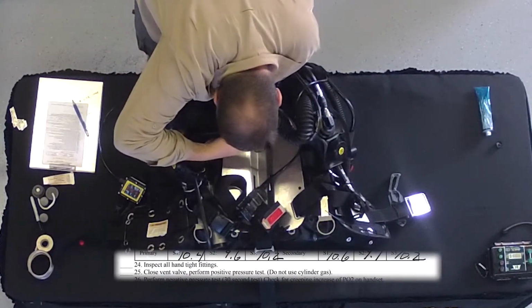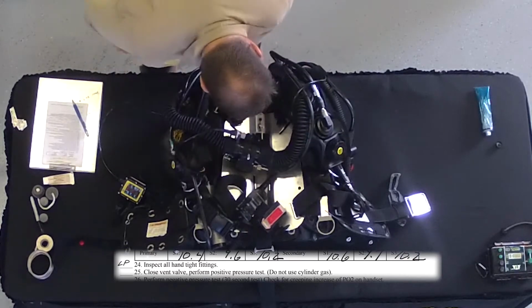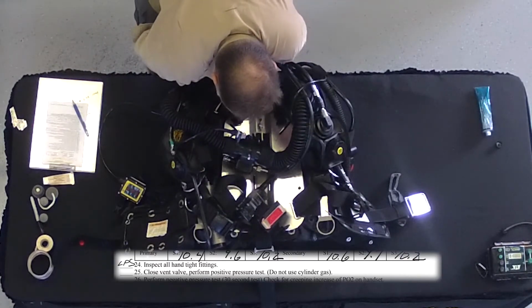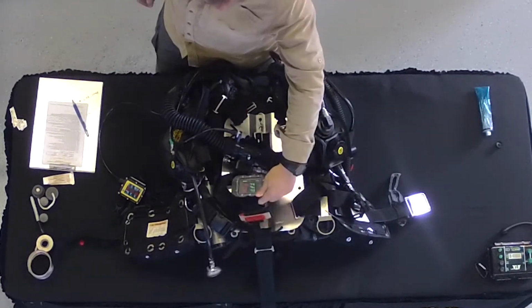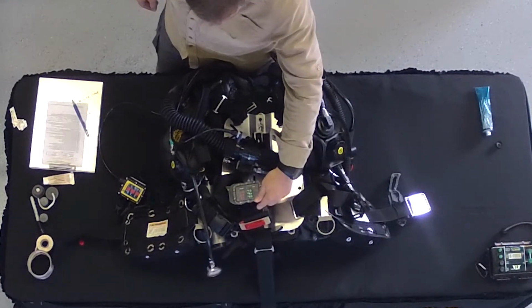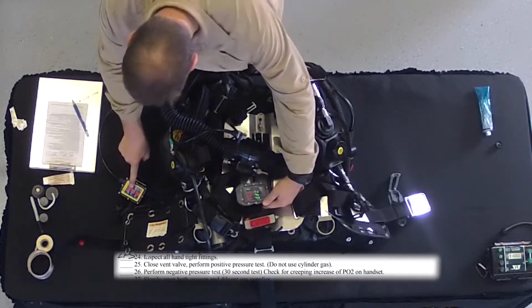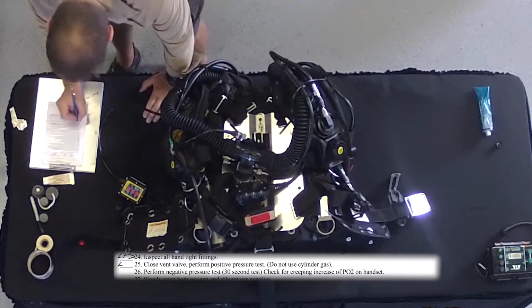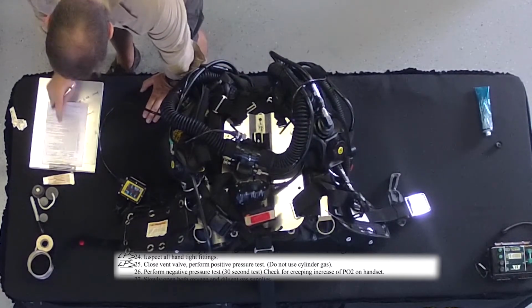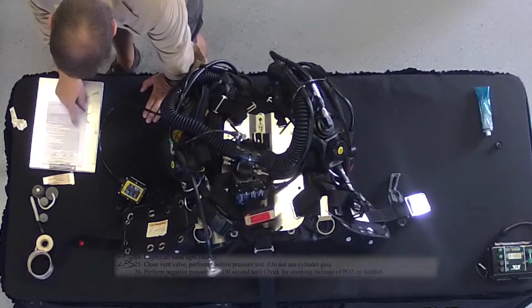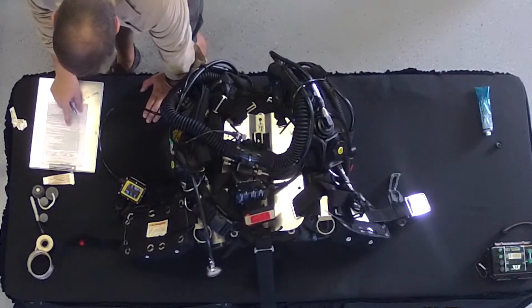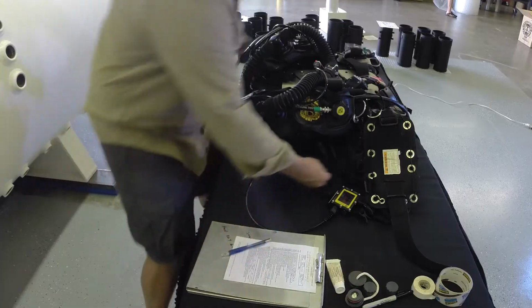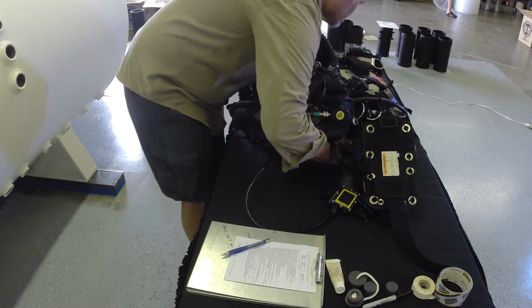Number 24, re-inspect all hand-tight fittings. Anything you screwed down must be rechecked to make sure they're tight. Number 25, you want to close the vent valve, perform positive pressure test. That means you're going to blow up the loop. It's full of ambient air. Don't use any air from the cylinders. Don't waste it. Just blow it up full of air.